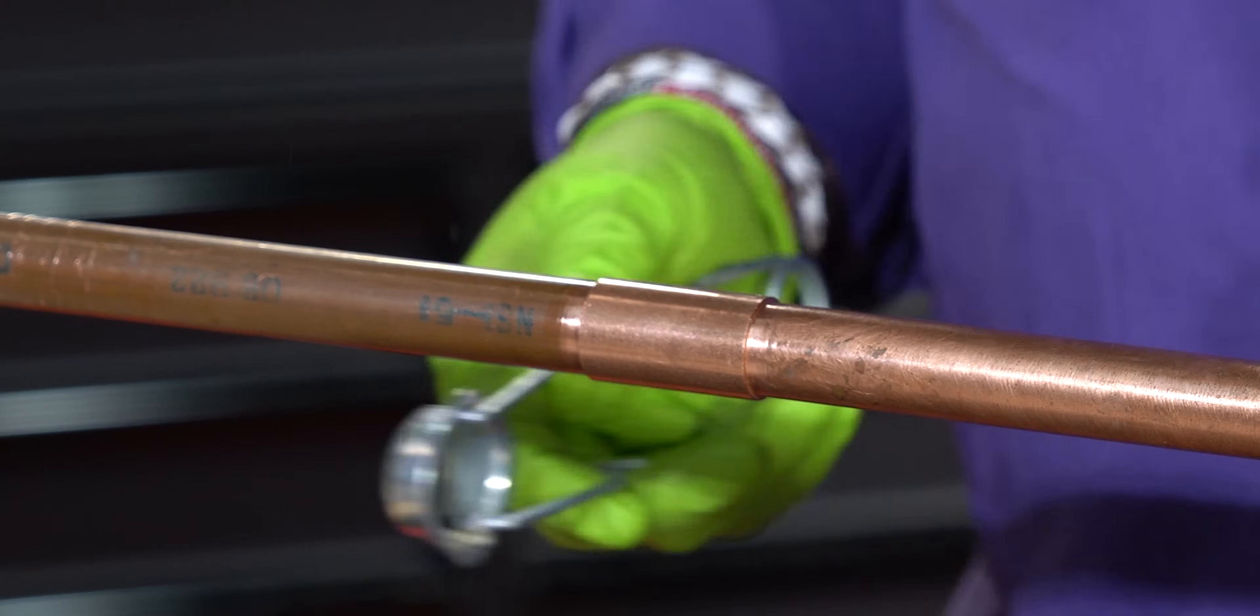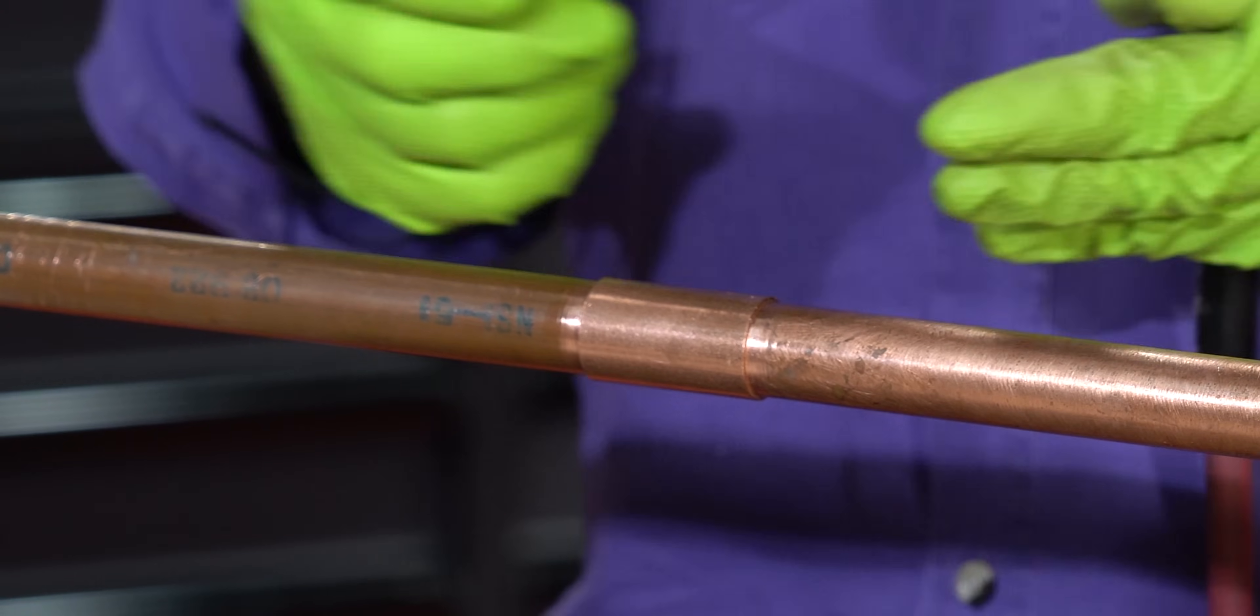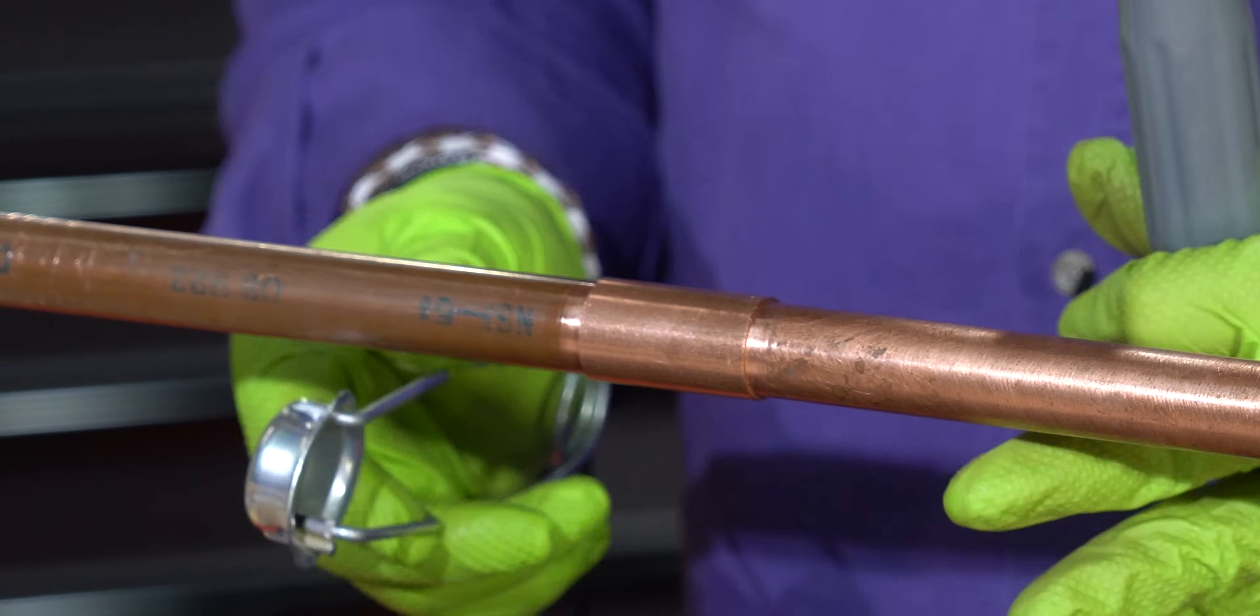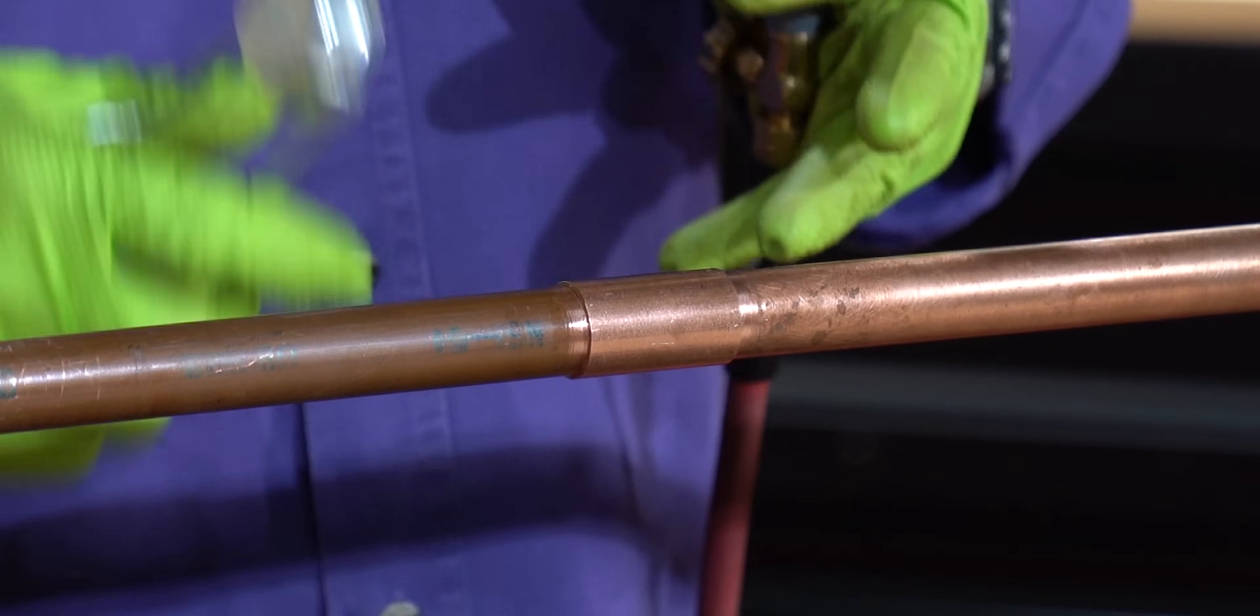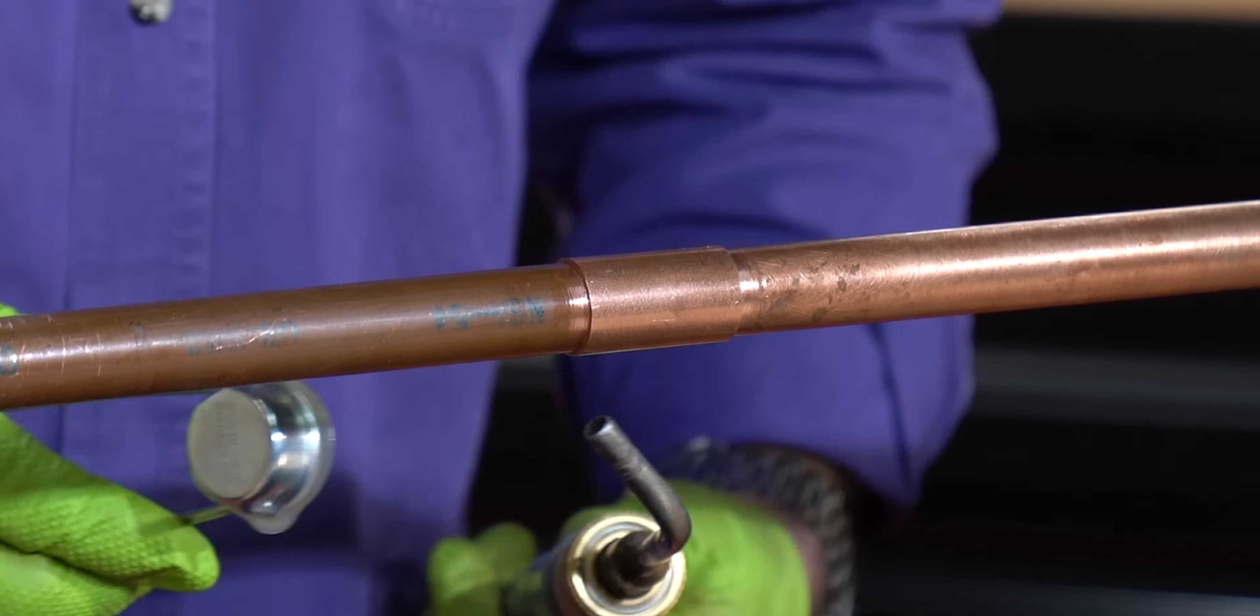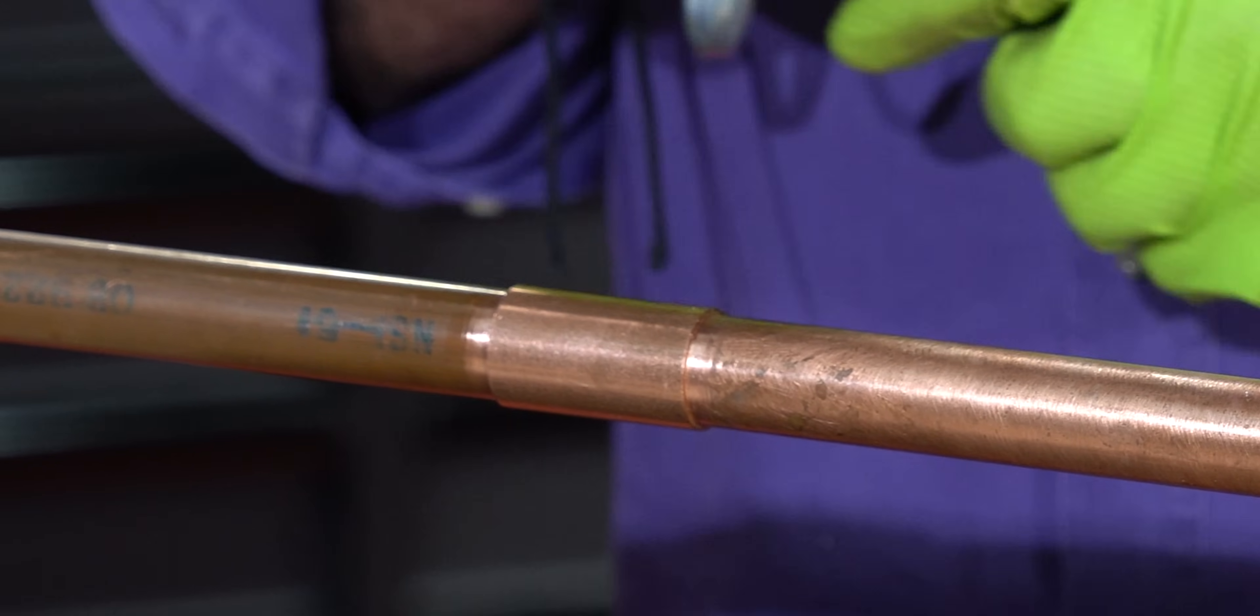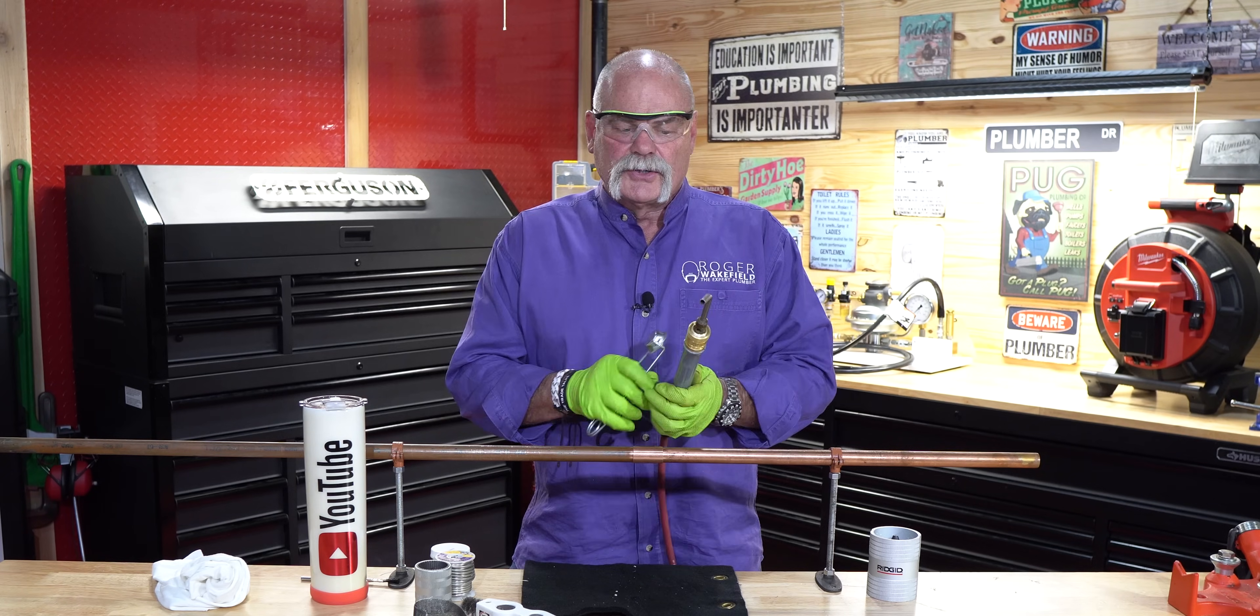Now, I may do things a little bit different. If I've got something I think may move, I may heat up the pipe first because I want the pipe to swell. That way I know nothing moves. Then I'd move my heat to the coupling, put it right here in the middle because that's where I want my solder to be drawn to. So let's go ahead and make a solder joint.